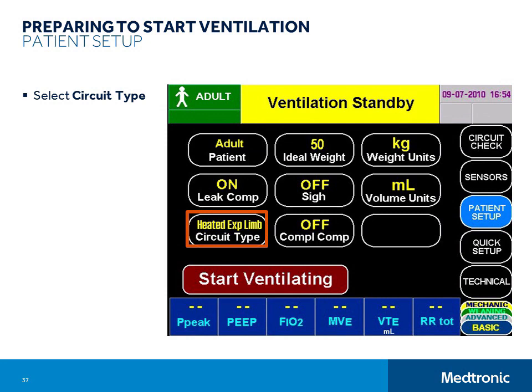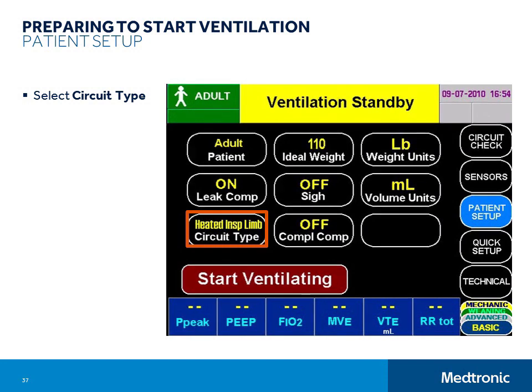Select heated expiratory limb when using a heated humidifier with a dual heated wire breathing circuit. Select heated inspiratory limb when using a heated humidifier with no heated wire on the expiratory limb of the circuit, whether or not you have a heated inspiratory wire on the inspiratory limb. Select HME when using a heat-moisture exchanger instead of a heated humidifier. And use test lung for demonstrating and testing the ventilator when it is connected to a test lung.